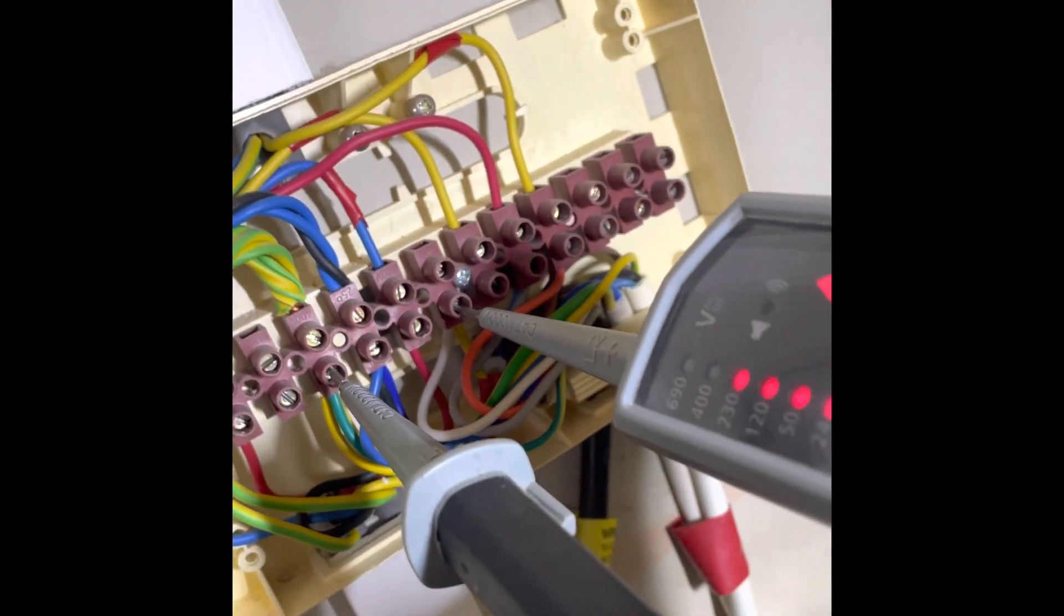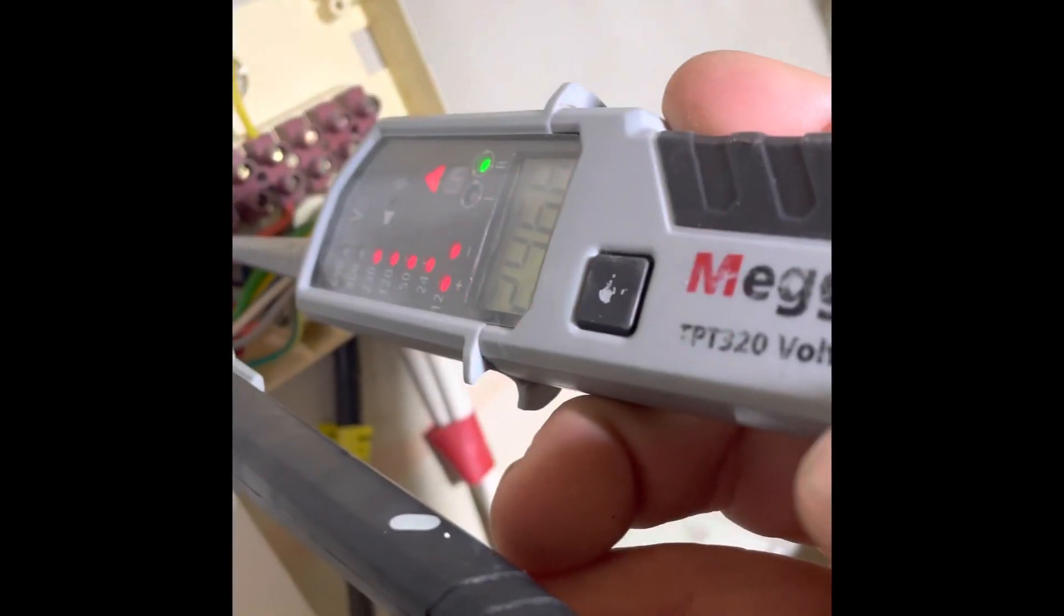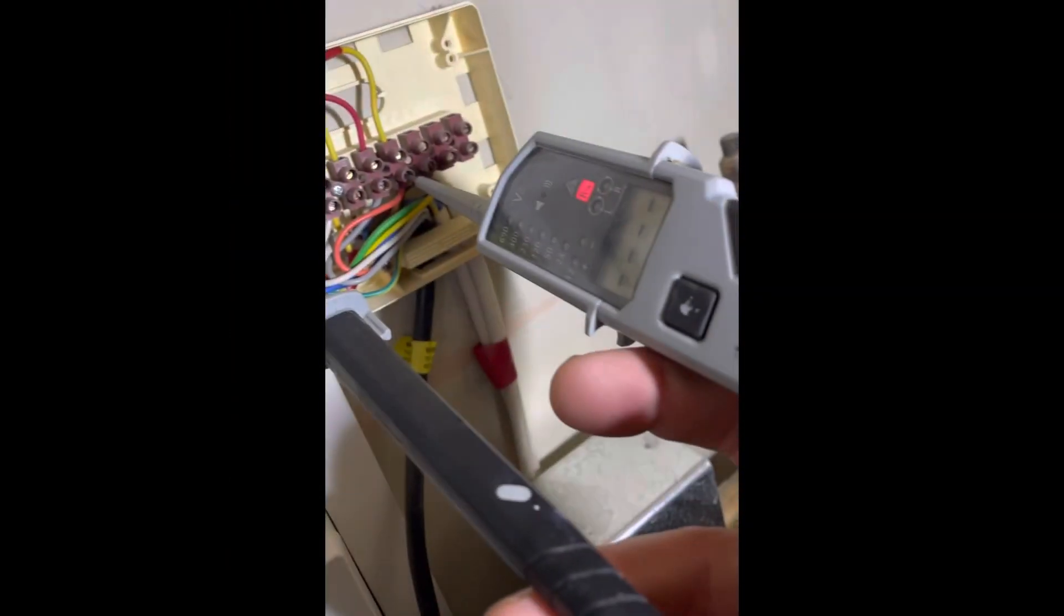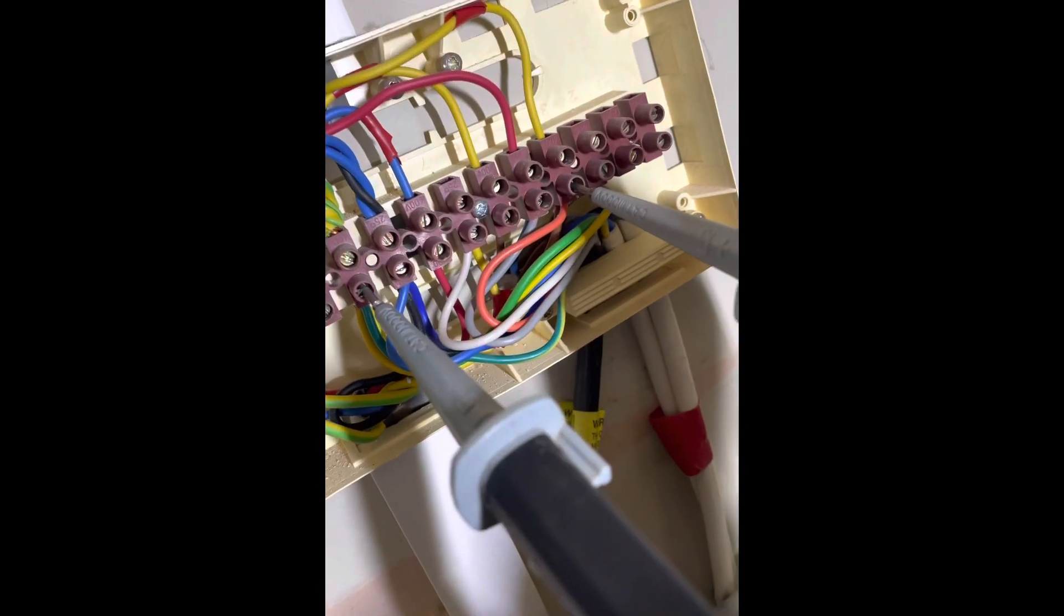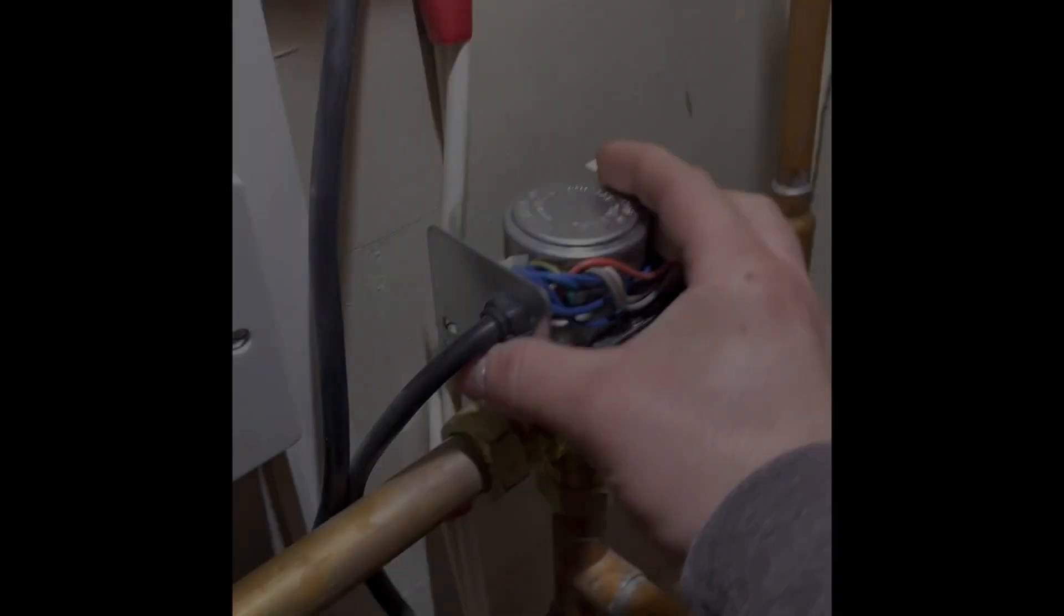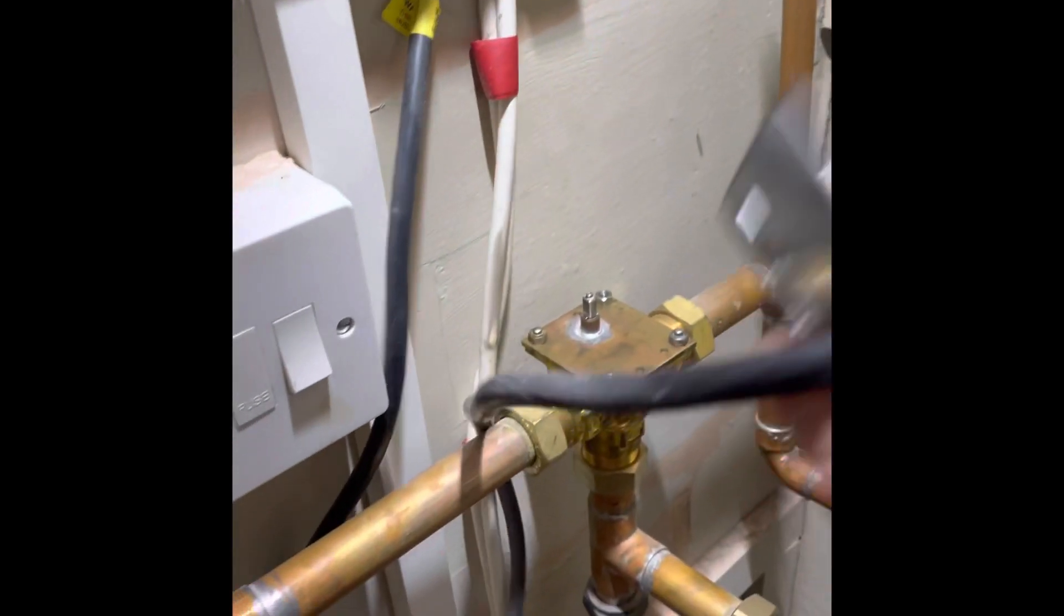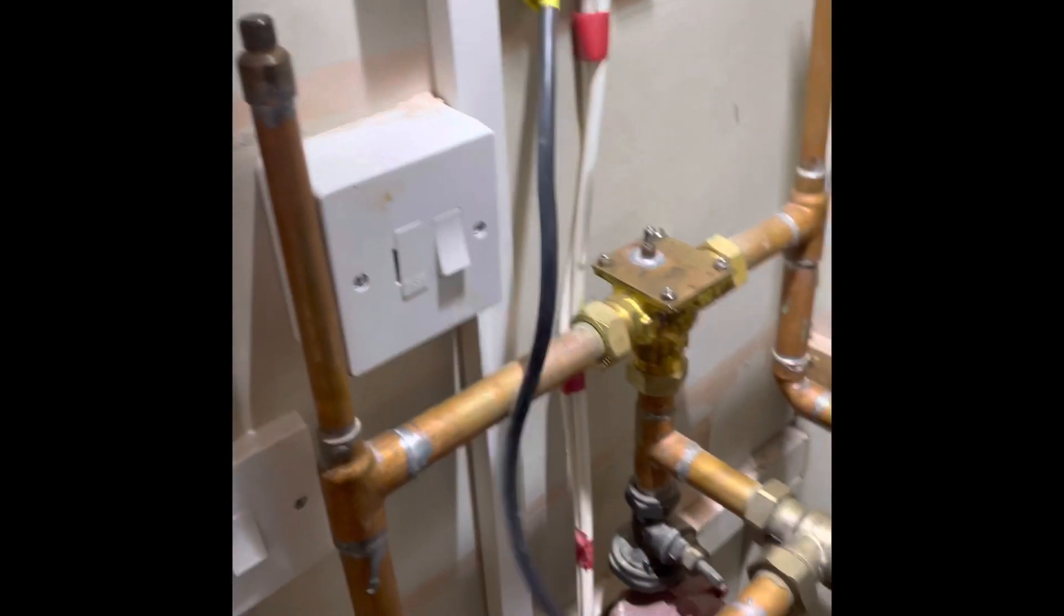Check to white, I got 240. Check to orange, nothing back. So it's a three-port valve head. Whip that off.